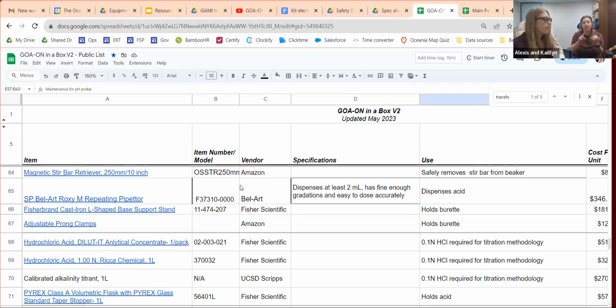Basically, what we're finding is it's usually the probe or the acid. If someone's having issues with their alkalinity that are pretty consistent and by a large margin, it's usually that the probe needs to be replaced or the acid concentration has somehow gone off. Even just swirling the acid as it's closed at the beginning of the day is important, because a little bit of evaporation or a little bit of water on the top can be an issue. So yes, hopefully the calibrated acid gets you on your way. If you start to find issues with the acid you've made, we can talk about how to adjust or remake it so it's the appropriate concentration.